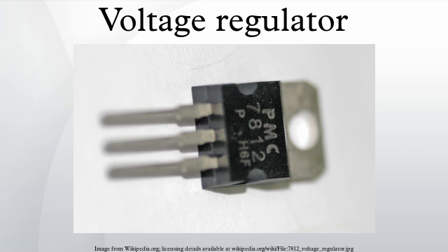How an AVR works: in the first place, the AVR monitors the output voltage and controls the input voltage for the exciter of the generator. By increasing or decreasing the generator control voltage, the output voltage of the generator increases or decreases accordingly. The AVR calculates how much voltage has to be sent to the exciter numerous times a second, therefore stabilizing the output voltage to a predetermined set point. When 2 or more generators are powering the same system, the AVR receives information from more generators to match all output.